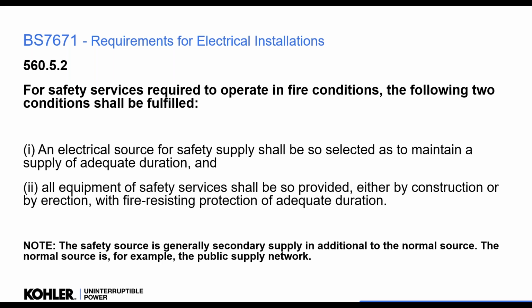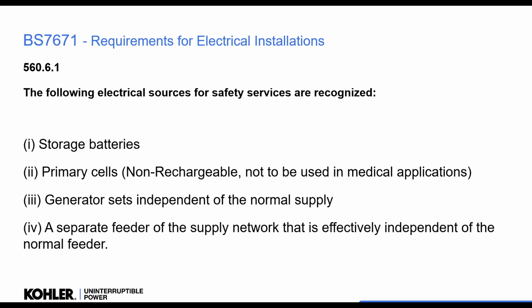duration as well. Okay, so the safety source is generally a secondary supply in addition to the normal source. Now, obviously, in a lot of healthcare situations, we have that, but there are obviously a lot of examples where that secondary source needs to be supplied, and we have to do that using storage batteries, primary cells, a generator set specifically for the life safety, or a separate feeder, if possible. Okay, not often available nowadays.